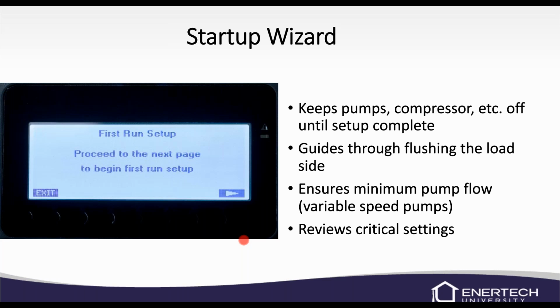Basically, this is what's going to happen. You're going to go into the first run setup. It's going to keep the pumps and the compressor off until setup is complete, and it will guide you through flushing of the load and the domestic hot water. It will ensure minimum pump flow on the variable speed pump, and we'll review some of the critical settings such as outdoor reset.